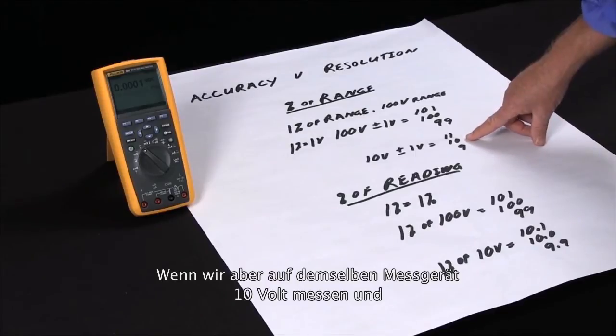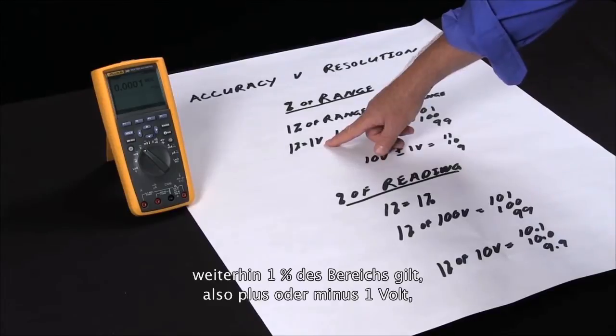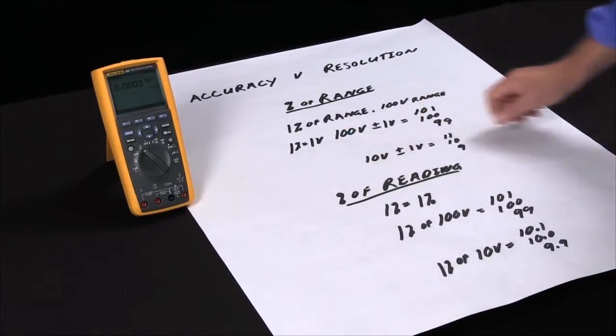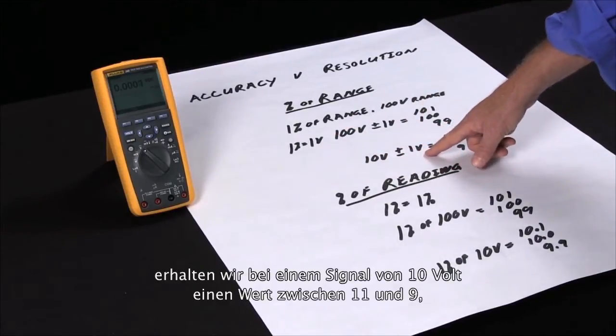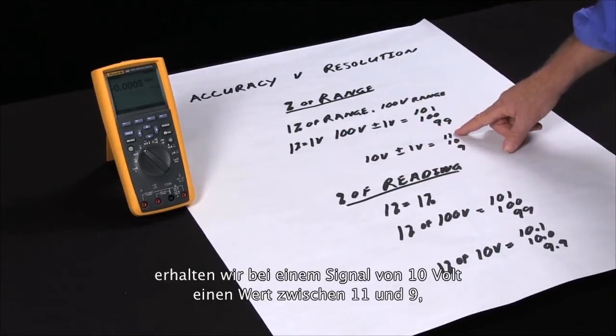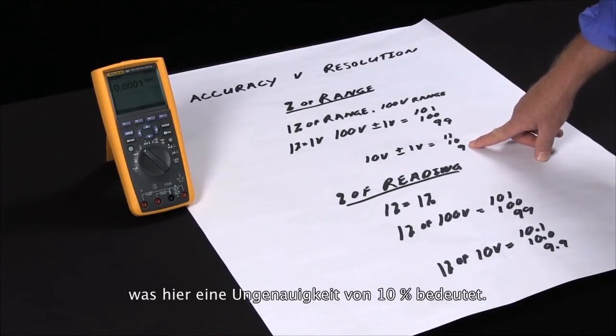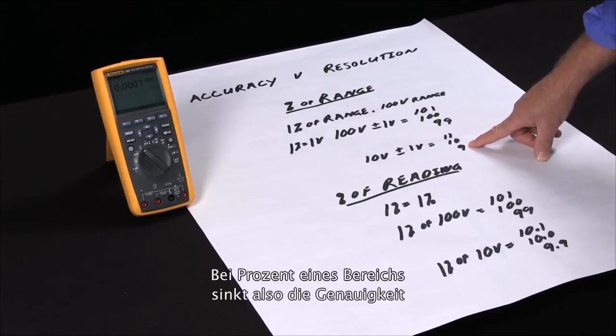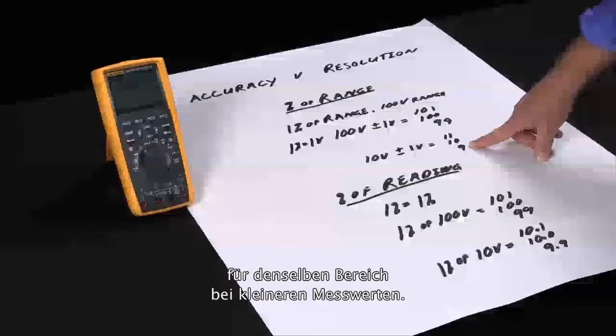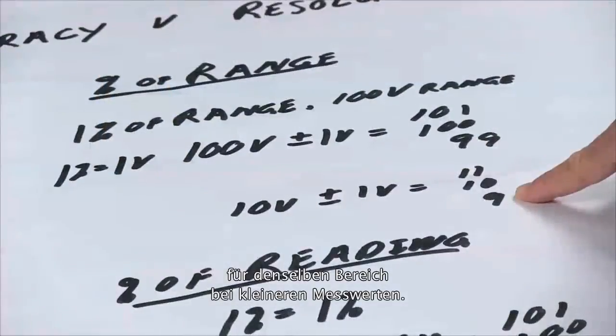But if we're measuring ten volts on this same meter, the one percent is plus or minus one volt. On a ten volt signal, plus or minus one volt gives us between eleven and nine, which is actually an inaccuracy of ten percent. So with percent of range, the accuracy actually decreases on the same range as you go down with the measurement values.